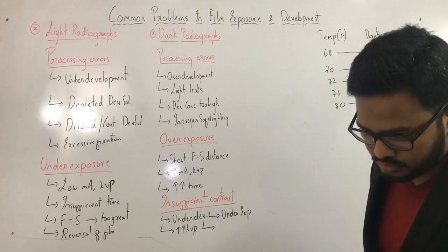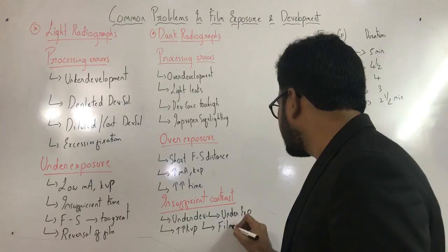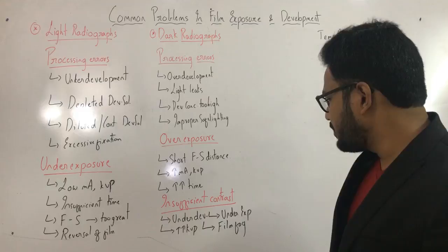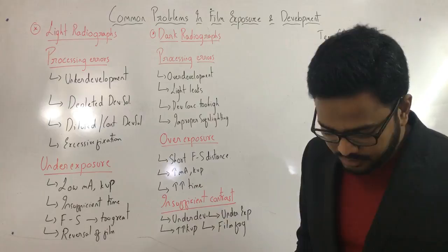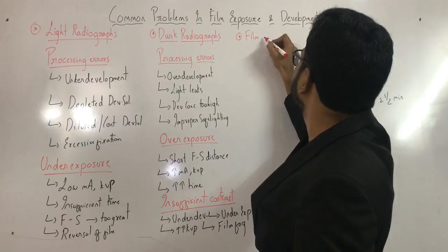Yes, and it's also mentioned that film fogging can diminish the contrast. Film fog. So underdevelopment, underexposure, or insufficient exposure, that's true. Or it can be increased tube potential or film fogging. So these are some of the reasons for your insufficient contrast. Now, coming to film fog.